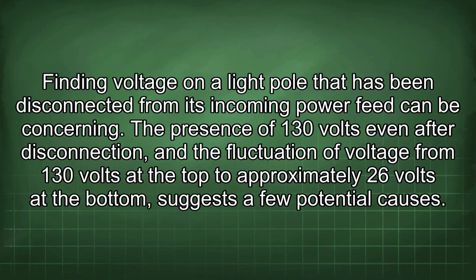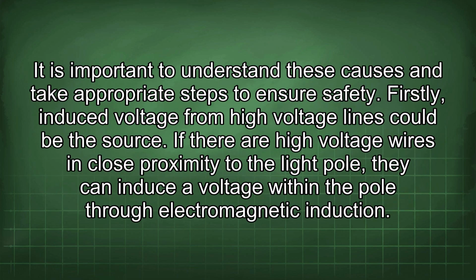Finding voltage on a light pole that has been disconnected from its incoming power feed can be concerning. The presence of 130 volts even after disconnection, and the fluctuation of voltage from 130 volts at the top to approximately 26 volts at the bottom, suggests a few potential causes. It is important to understand these causes and take appropriate steps to ensure safety.